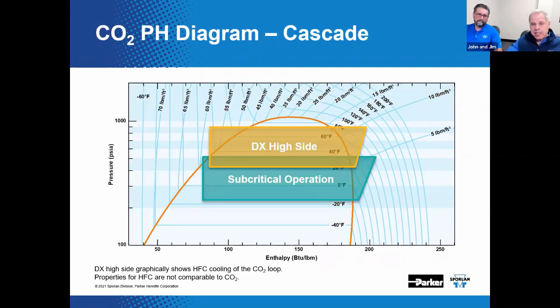Here is the cascade system superimposed on the PH diagram for CO2. The HFC refrigerant would be used on the high side to ultimately reject heat transferred from the caseload to the ambient or to some other place. That's what's depicted here. In that regard, this system is similar to the previously discussed liquid overfeed secondary application. The CO2 will be expanded and evaporated on the low side to provide the refrigerating effect in order to handle the caseload. It's considered cascade because two or more vapor compression refrigeration cycles are used with different refrigerants while being interconnected with a heat exchanger. We'll show that to you in just a second.